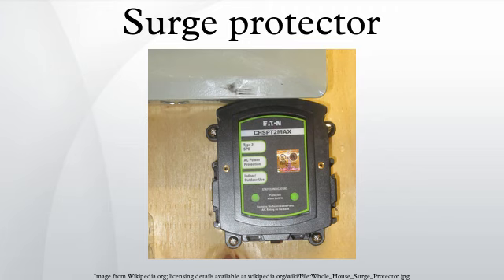Thus, the effective surge energy absorption capacity of the entire system is dependent on the MOV with the lowest clamping voltage, and the additional MOVs do not provide any further benefit. This limitation can be surmounted by using carefully matched sets of MOVs, but this matching must be carefully coordinated with the original manufacturer of the MOV components. According to industry standards, power line surges inside a building can be up to 6,000 volts, 3,000 amperes, and deliver up to 90 joules of energy, including surges from external sources. Lightning and other high-energy transient voltage surges can be suppressed with a whole-house surge protector.